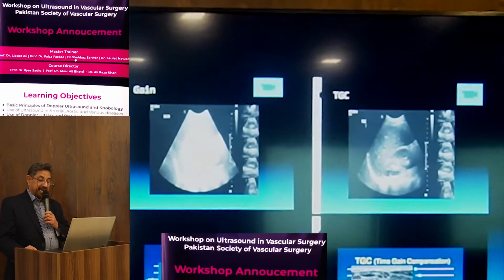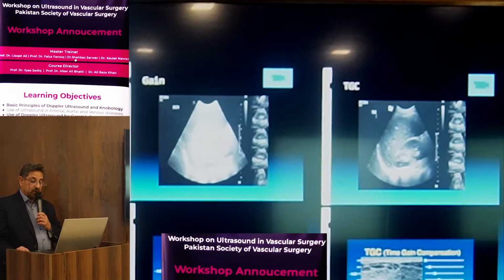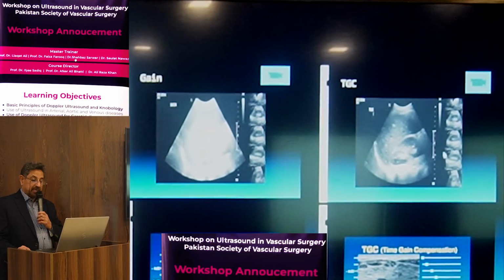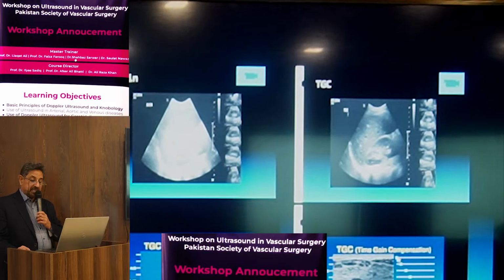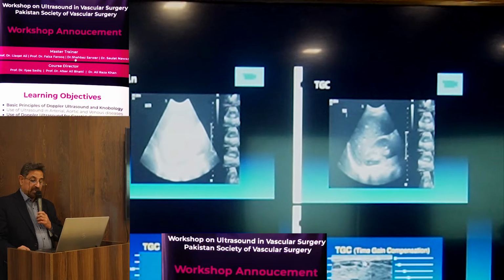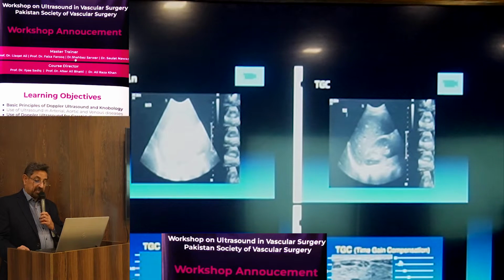To do that, we keep the time gain compensation in such a manner that echoes coming from the nearest part of the body are compensated minimally, but those coming back from the farthest part get maximum compensation.